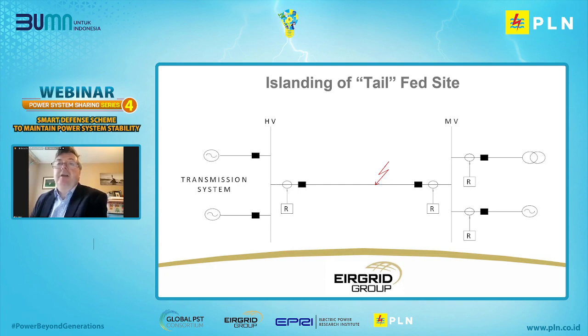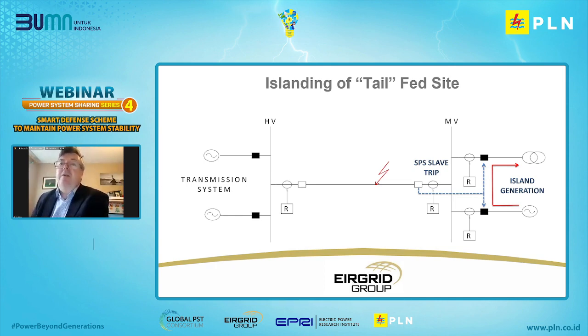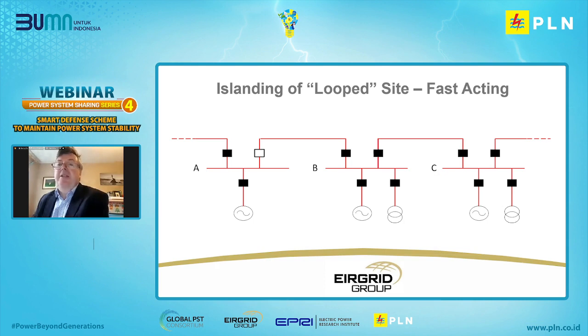So here we're showing a fault on the feeder itself. So the feeder's protection will open both ends of this feeder. So if you just go to the next slide, please. Yeah, so now the breaker at the remote end tailfed station has opened because of a feeder fault. Again, that change in status of the breaker is picked up, and it's then relayed to the other breakers connecting the generation and load transformer. So obviously the point to make there is the loss of the tail feeder is creating an island.